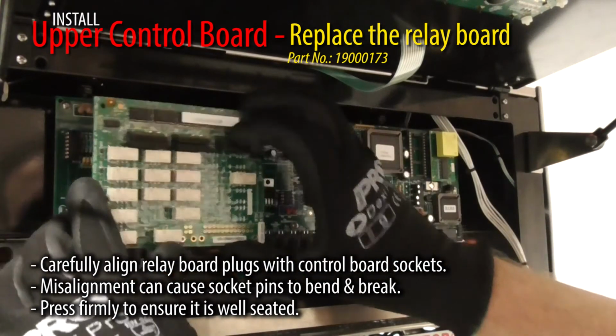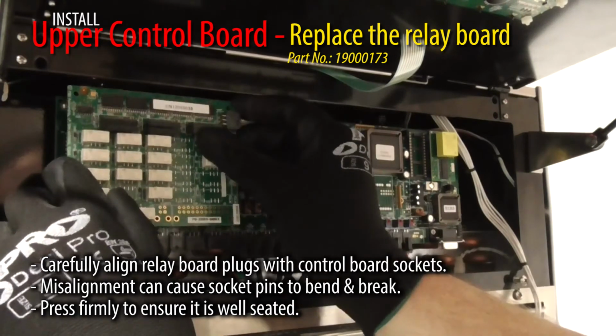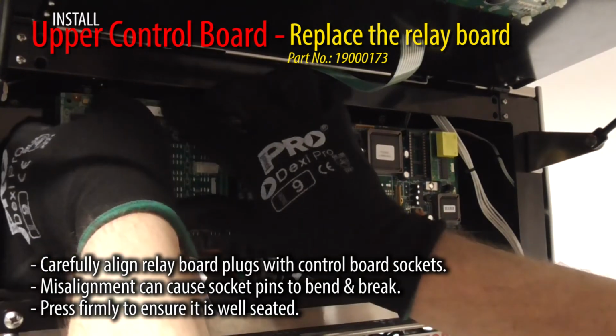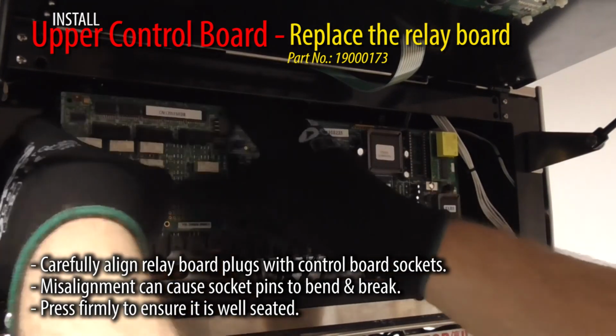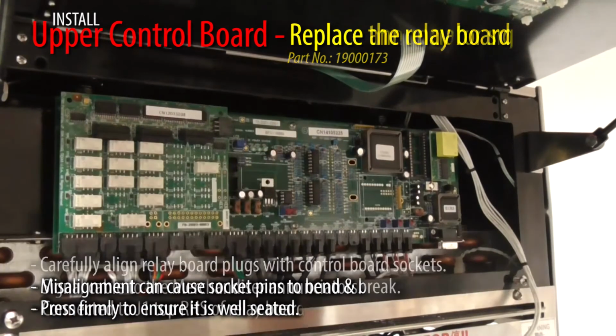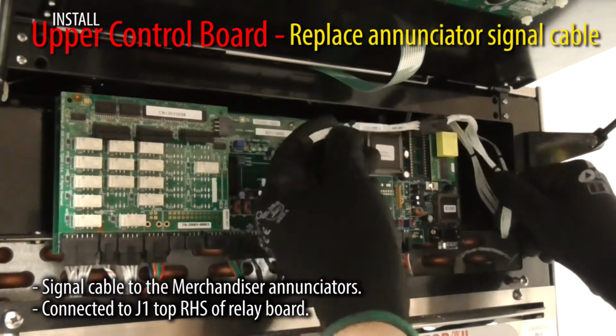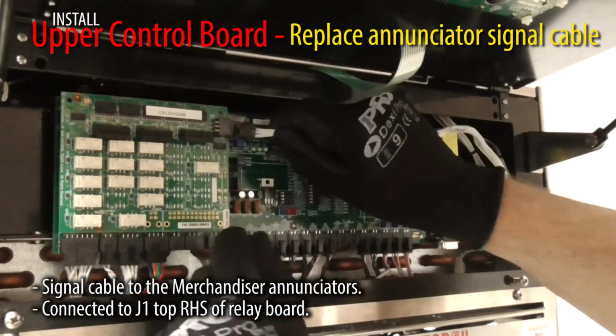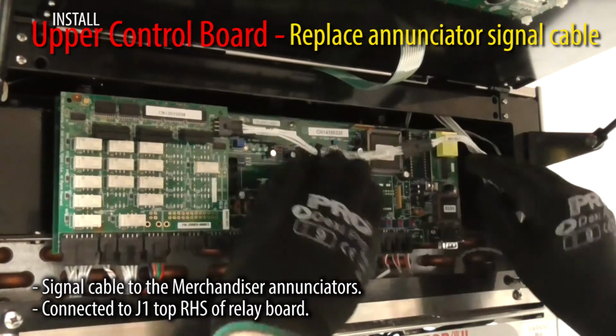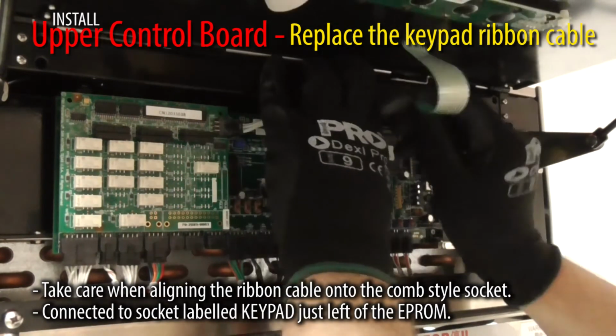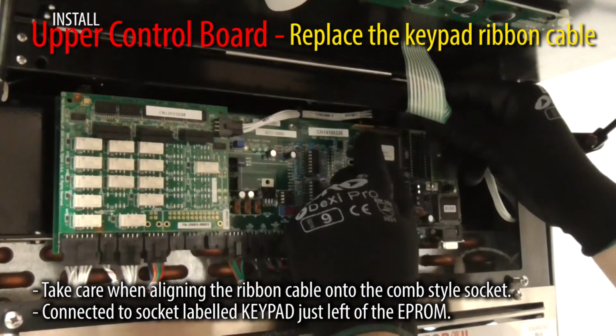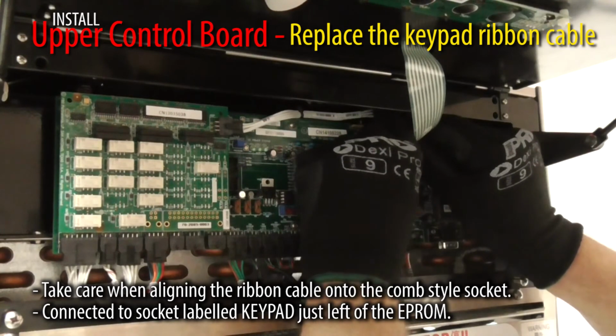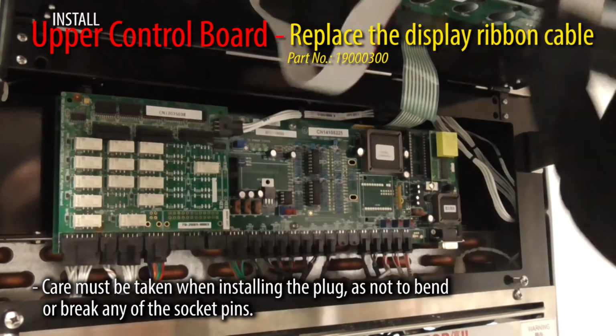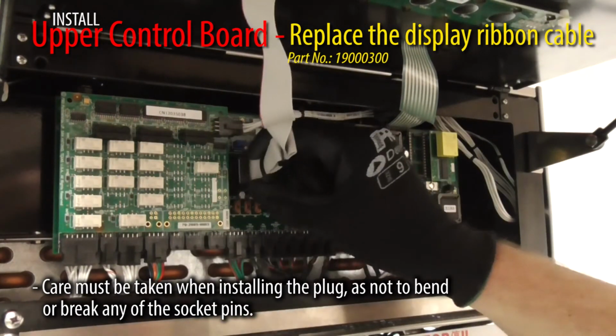Replace the relay board, taking care to align it correctly as not to damage any pins in the sockets, and ensure it is firmly seated into the upper control board. Replace the annunciator signal cable, tuck it in behind the board, and then secure the plug into socket J1 on the relay board. Carefully realign the keypad ribbon cable plug into the comb style socket. Take care connecting the display ribbon cable as not to damage the socket's pins.